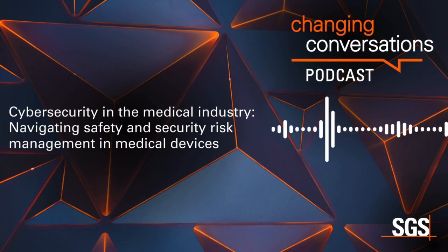That's actually a really interesting question, because as a TIC company, the question of how we judge things is a very crucial one in our daily business. During IEC 60601 evaluation, besides basic safety requirements, we strongly focus on essential performance features. In many cases, specific limits are defined by particular standards and have to be maintained under what, in our language, is called normal and single fault conditions. For example, if you have a ventilator and you apply a certain pressure, then you need to be sure that it stays within certain limits and does not harm the patient. This is really crucial. We have a clear cut here.